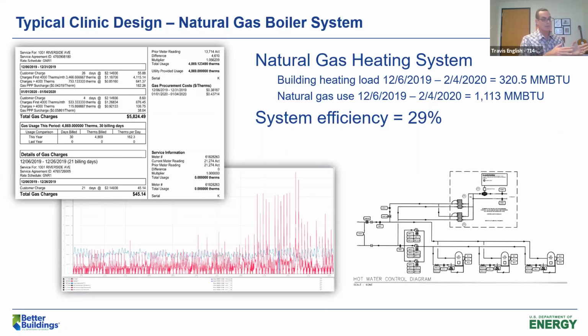But when we put them into buildings, we tend to oversize them. We connect them to pumping systems with a bunch of zone controls that introduce a lot of inefficiency. This is a study we did on another building for its first winter, during the coldest months of the year. The heating system here is operating at like 30% efficiency, not 95%. There are some corrections we can apply, and this system may operate up to about 50% efficiency, but the point is it's way off of the energy model. It's not 95% at all, not even 80% — it's down to sub-50% efficiency.